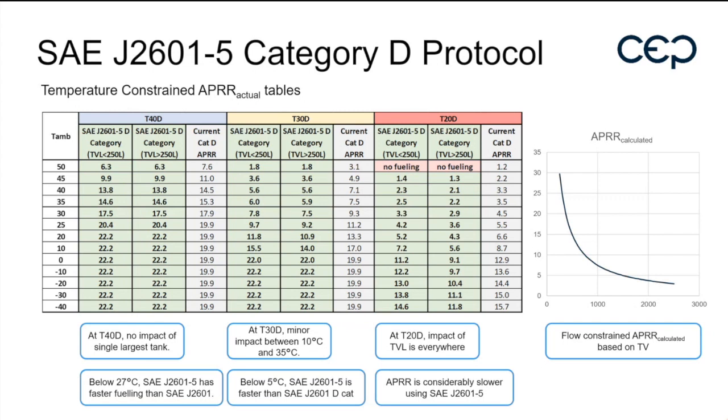Initially, our plan was to do anything between FM60 and even FM120, even though there might be only a 4 millimeter design receptacle. And of course, this would create a much higher pressure drop. But that was the original intention. And in the end, we decided, for the sake of simplicity and also in order to reduce the testing, to choose only FM60 or FM90.